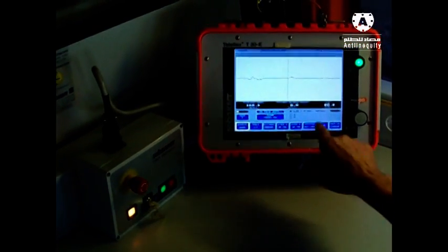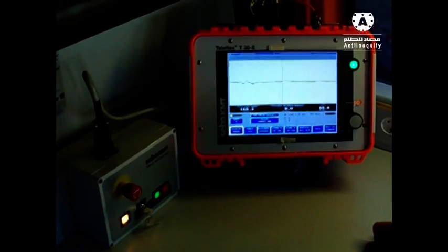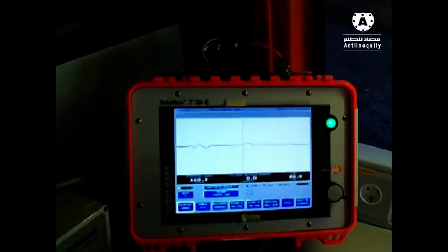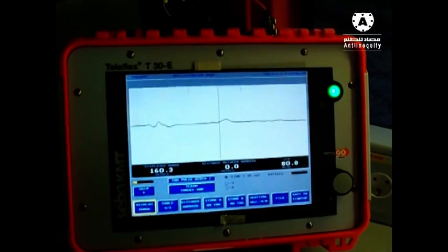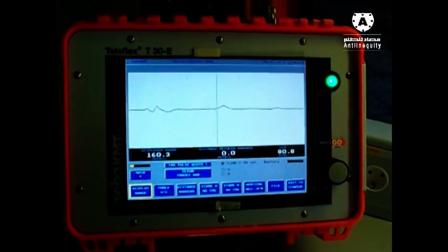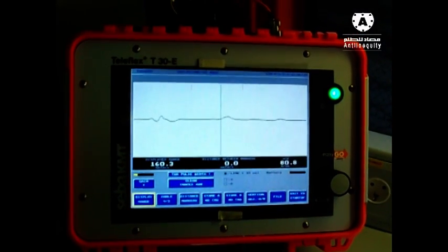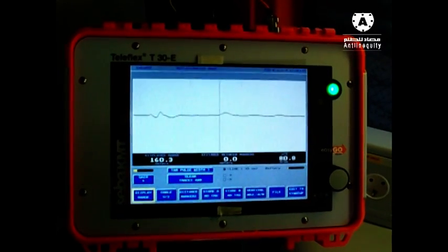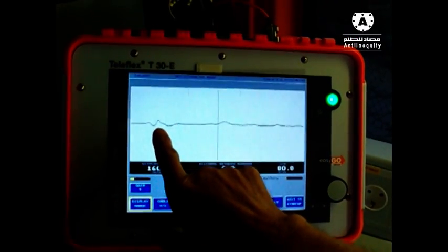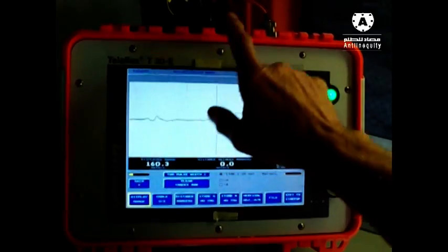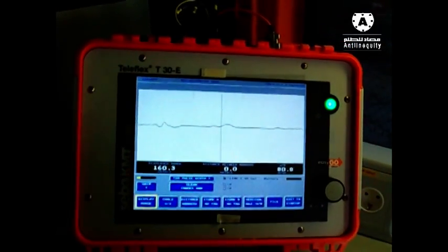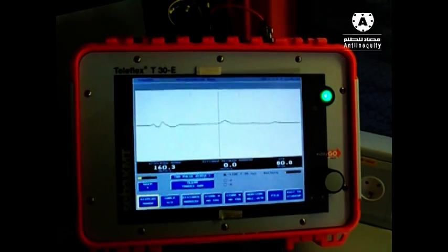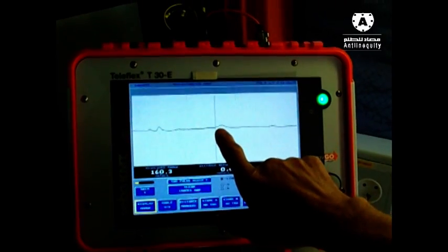The first is we have to adjust our picture. If you know the real cable length, you must adjust first the display range. In our case now we have connected at our cable from the test van cable drum only a spark gap. That means our cable is not longer than 50 meters. What we see now on the screen is, this is our beginning impulse. This is the impedance change from here through the system and the connection point of our cable drum, high voltage cable drum, and this should be our cable end.